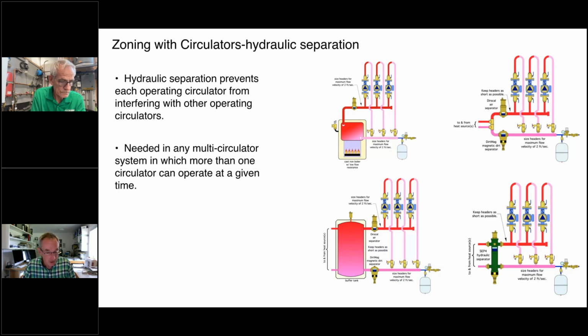A buffer tank can provide it. And then finally, you've got, in this case, the SEP4 hydraulic separator, which gives you hydraulic separation, but it also gives you air, dirt, and magnetic particle removal. So this replaces the separate components for air separation and magnetic dirt separation. Any thoughts on this, Hot Rod?